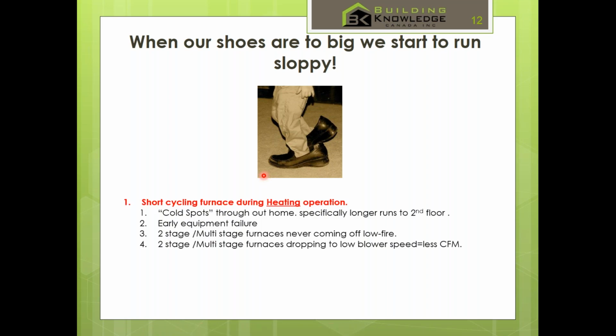When you short cycle during heating season, you start to get cold spots and severe stratification, because when the furnace comes on and the heat exchanger comes on, it hits its high temperature limit, satisfies the thermostat and shuts off, and yet the fan never runs long enough to move enough air through the system on the longest run to either the back bedroom on the second floor or the good old rooms over the garage. We've seen situations where by the time the cycle shuts off, the longest run in the house, which again is typically on the second floor or an outlying bedroom in the corner of the house, has only seen about 25 to 30% of its heat load met, because the air in the ductwork is still too cold. Meanwhile, the center of the house is warm.